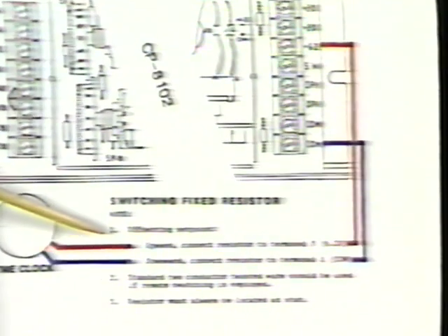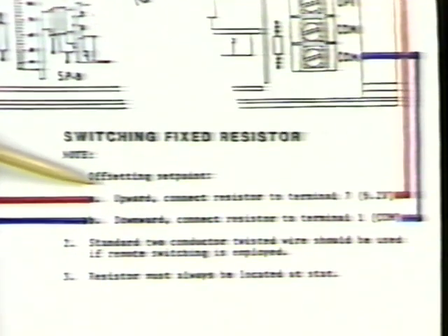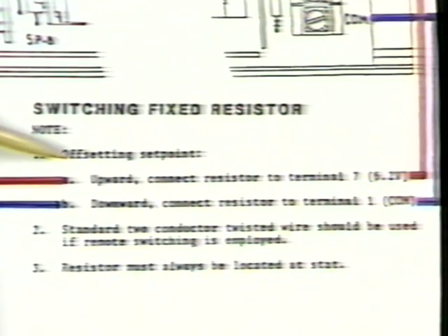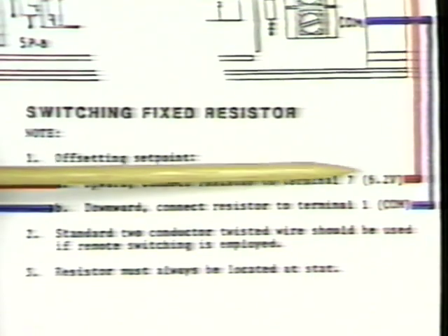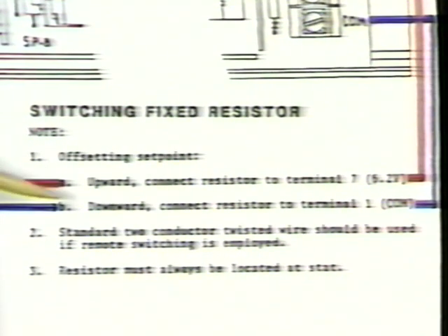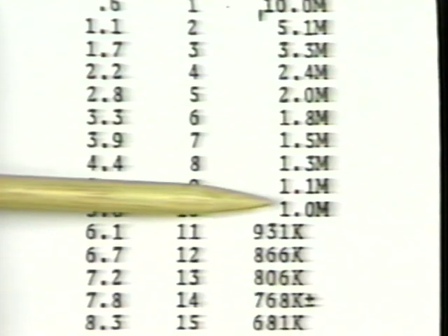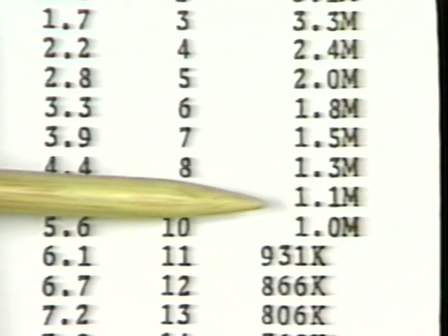The arrangement is as follows. To offset the set point upward, that is a higher set point, the time clock will close between AB1 and 6.2 volts. To set the set point back or downward, the time clock will close between AB1 and common. This chart shows the relationship between degrees of offset in Celsius or Fahrenheit and the resistance value for the resistor in the circuit. For a typical 10-degree offset, a 1.0 meg-ohm resistor is required.